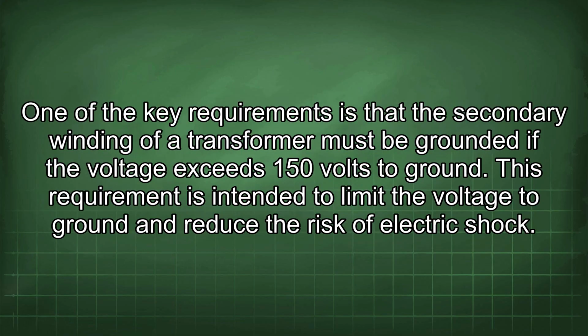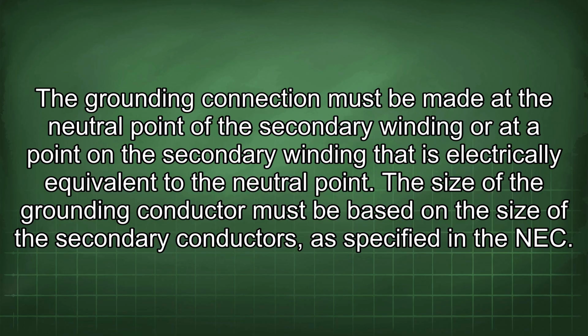One of the key requirements is that the secondary winding of a transformer must be grounded if the voltage exceeds 150 volts to ground. This requirement is intended to limit the voltage to ground and reduce the risk of electric shock. The grounding connection must be made at the neutral point of the secondary winding or at a point on the secondary winding that is electrically equivalent to the neutral point.